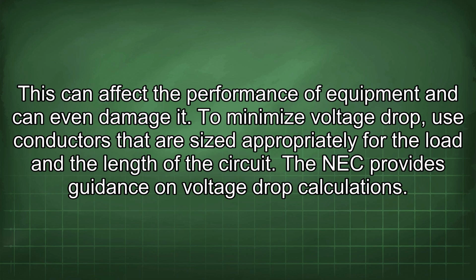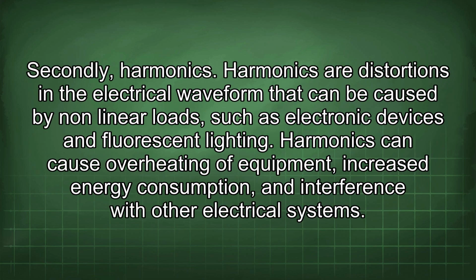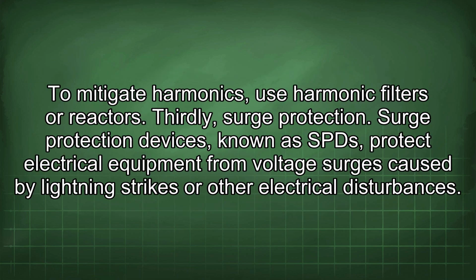To minimize voltage drop, use conductors that are sized appropriately for the load and the length of the circuit. The NEC provides guidance on voltage drop calculations. Secondly, harmonics. Harmonics are distortions in the electrical waveform that can be caused by nonlinear loads such as electronic devices and fluorescent lighting. Harmonics can cause overheating of equipment, increased energy consumption, and interference with other electrical systems. To mitigate harmonics, use harmonic filters or reactors.